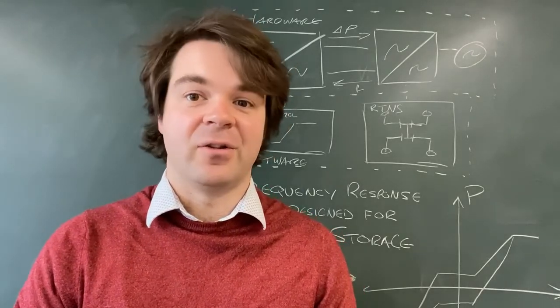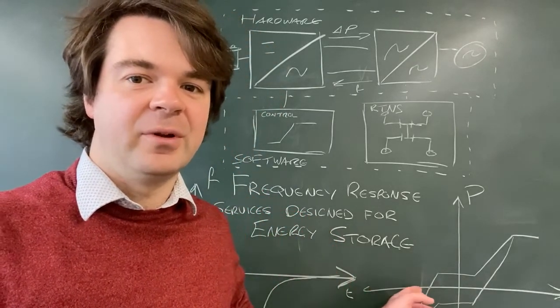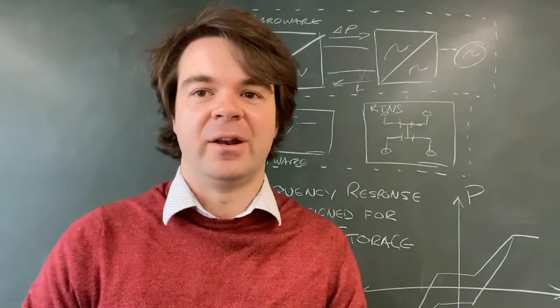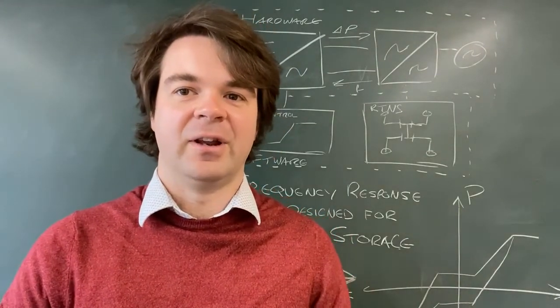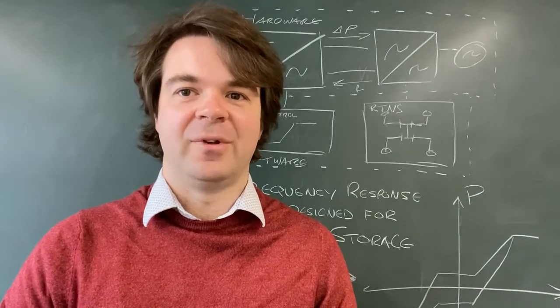and we found that the energy storage could effectively manage its state of charge by having an envelope in its required response rather than a fixed line that it has to follow, as is the case with conventional response type technologies.